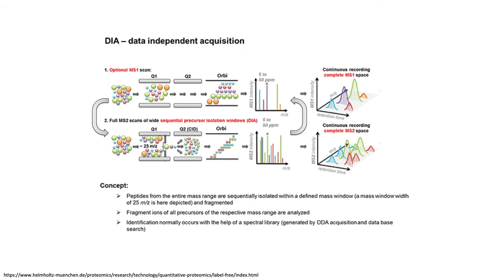In contrast, in the data-independent scan, the ions again go into the quadrupole, a full mass spectrum is analyzed, and then sequential precursor windows are isolated, and all of the ions that fall within that mass range are isolated, fragmented, and a mass spectrum combined. These mass windows tend to be on the order of 4 to 25 m/z units, so you get a combined picture of everything that's present. Nothing is lost, there's no limit on the number, but the linkage between the parent ion mass and the fragment ion mass is lost.